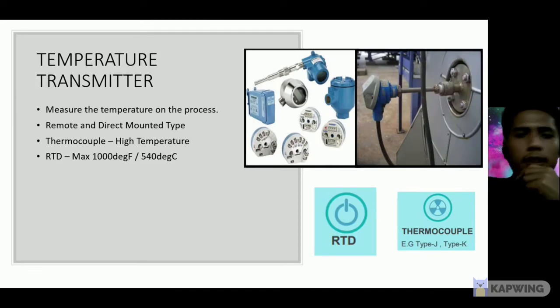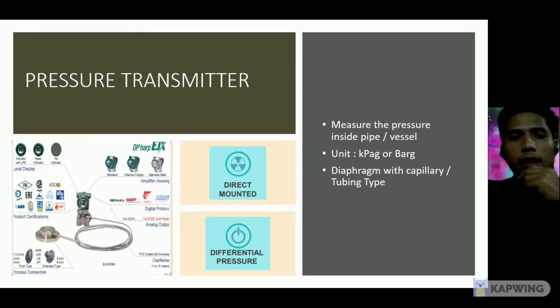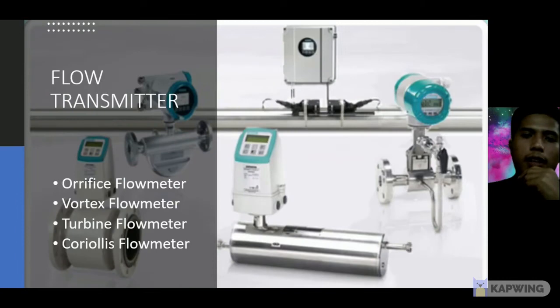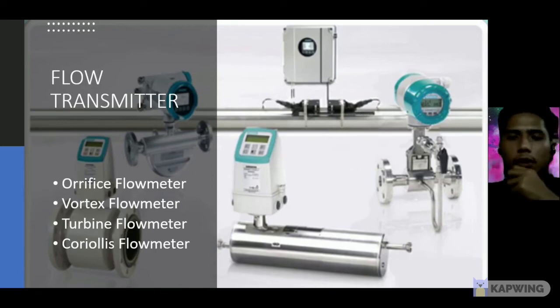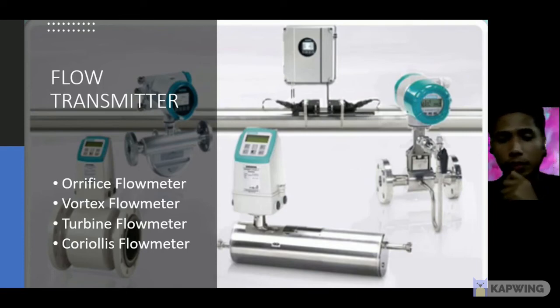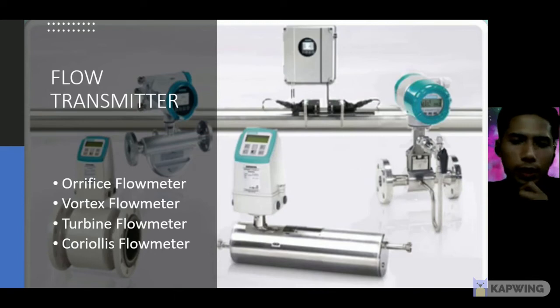Next, temperature transmitter. Measures the temperature of the process, remote and direct mount type. Thermocouple for high temperature, RTD max 1000 degrees Fahrenheit or 540 degrees Celsius. Pressure transmitter. Measures the pressure inside a pipe or vessel. Unit used is kilopascal or bar. Diaphragm with capillary or tubing type. Next, flow transmitter. It has many types of flow transmitter, but the best for use are the orifice flow meter, vortex flow meter, turbine flow meter, and Coriolis flow meter.